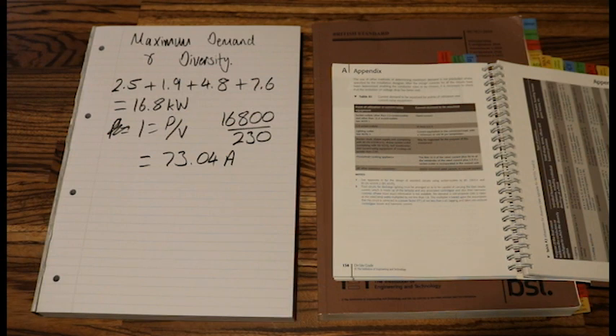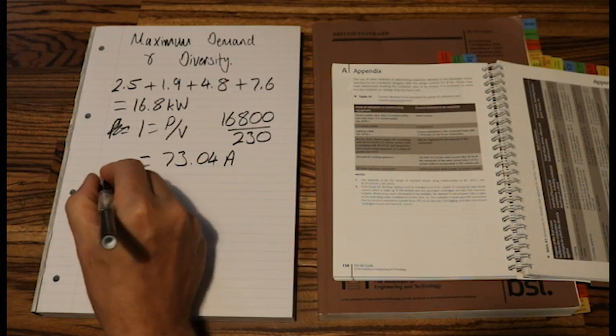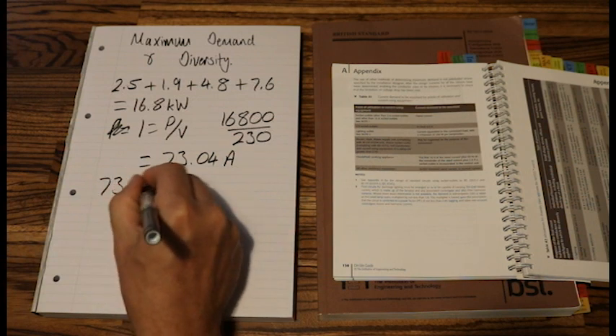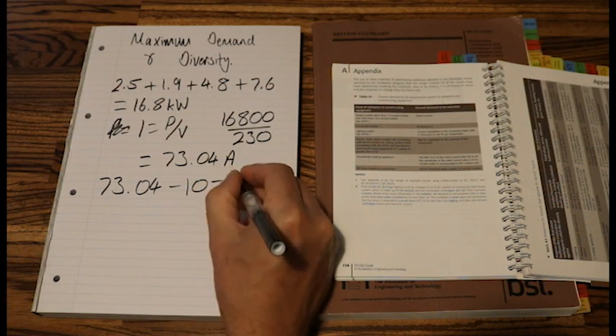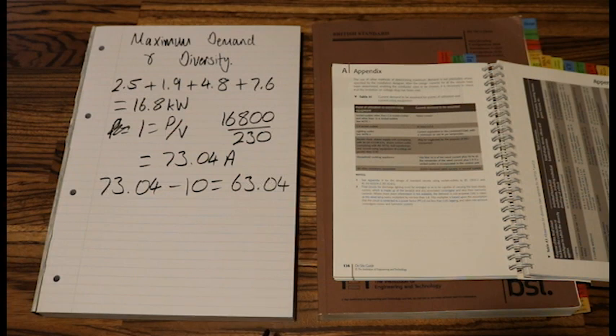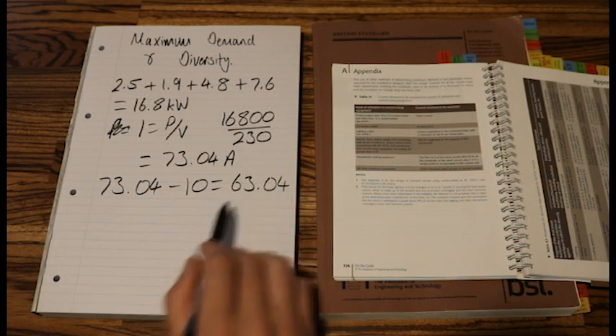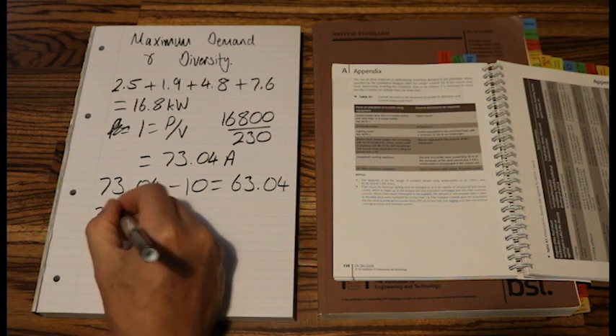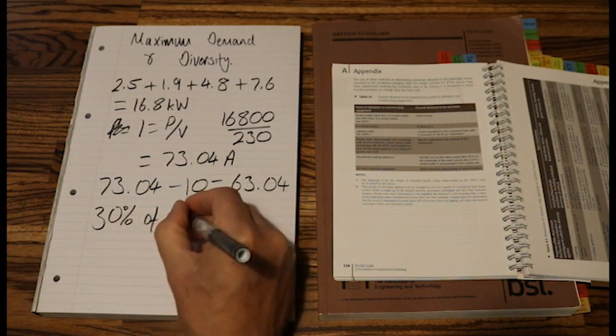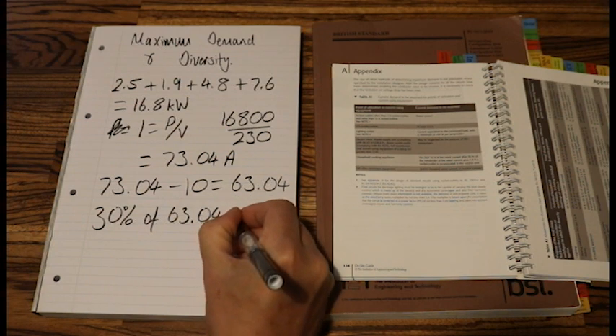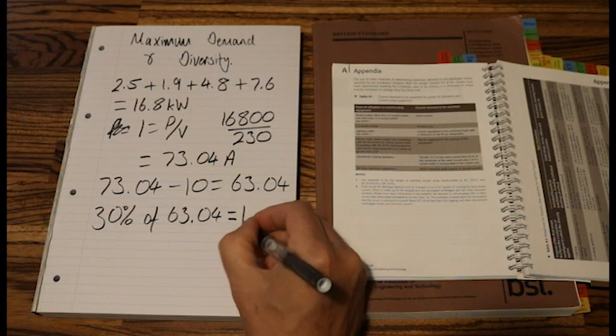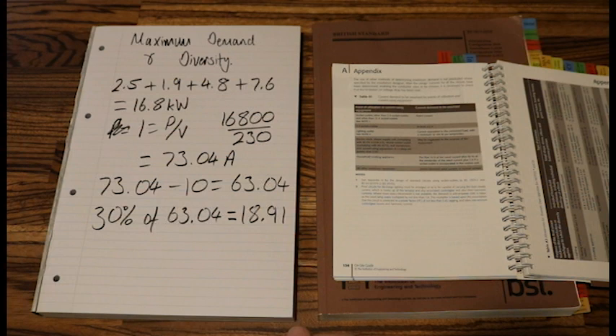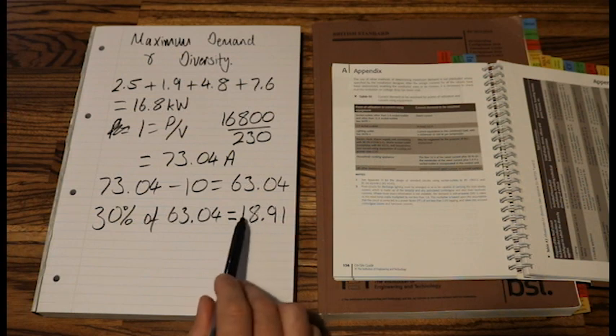Now we need to apply the diversity that table A1 set. So we take the first 10 amps, and we need to work out 30% of the remainder. So we've got to do 73.04 minus 10 equals 63.04. And we want to work out 30% of the remainder, so 30% of 63.04 equals 18.91.